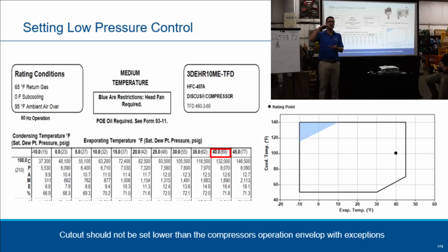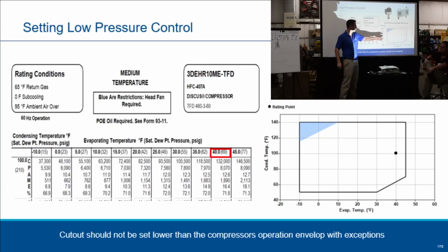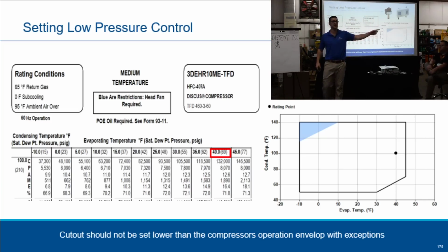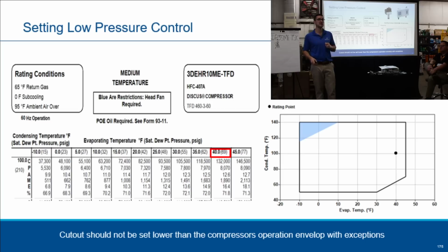Starts to rise, right? So then it starts a short cycle. So then you could try down to 20, which is 42 pounds. Because you don't want the short cycle and recycle a lot of times, right, as that pressure rises. You could actually just, if you want, put it right to 15, because you're still inside that operation envelope, right? If you put it down to 15 and all of a sudden it starts to rise really quickly, and you got a short pipe run, what could be an issue if it's a semi-hermetic? Bad valves. Awesome. What's your name? David. David, thank you very much.